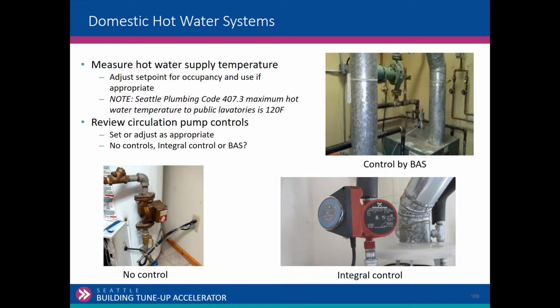If there are circulation pumps, do they have control? Is it plugged into the wall? There's no control there, but there's maybe an opportunity. We're not requiring that you install a control, but there are plug-in timers that you could plug in here and turn that pump off at night. So it's a relatively low cost measure. Is it controlled by the BAS? And if it is, does the schedule match occupancy? A lot of the newer buildings now, under the new codes, require that the pumps be controlled by not only schedule, but demand. So if there's an aquastat, does the set point of the aquastat make sense, so it shuts the pump off?